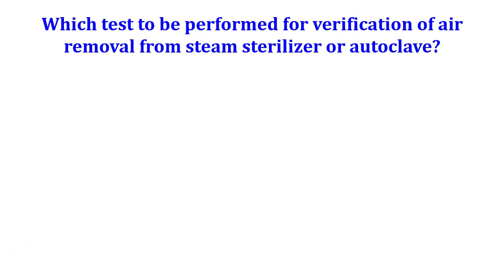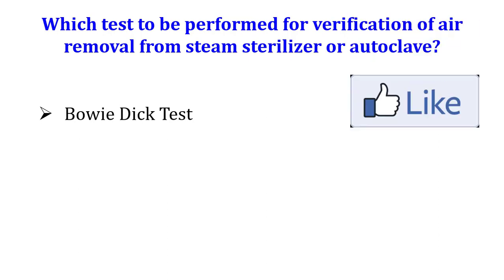So which test is to be performed for verification of air removal from a steam sterilizer or autoclave? This test is called the Bowie-Dick test, and it is performed to check the efficiency of air removal from the steam sterilizer.